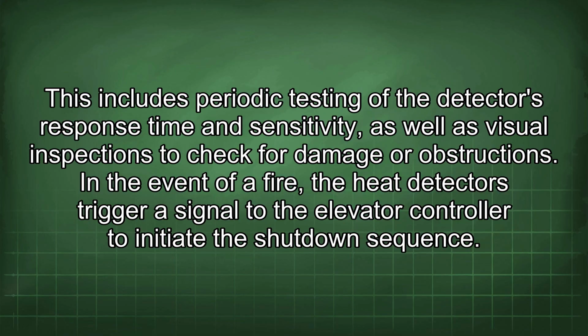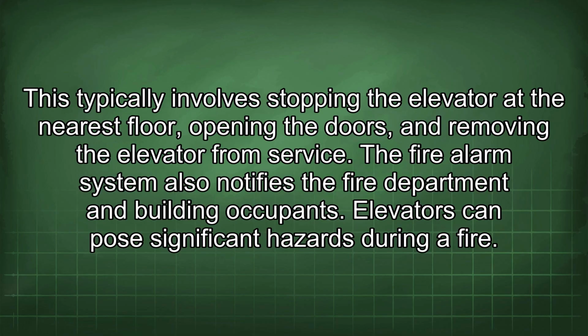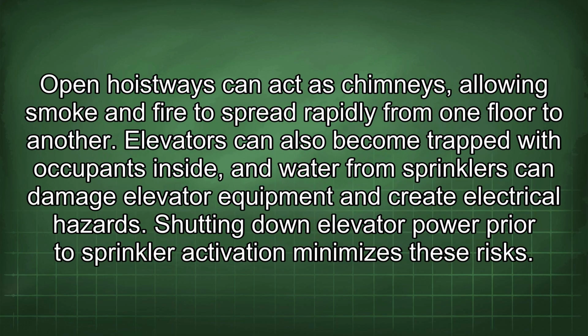or obstructions. In the event of a fire, the heat detectors trigger a signal to the elevator controller to initiate the shutdown sequence. This typically involves stopping the elevator at the nearest floor, opening the doors, and removing the elevator from service. The fire alarm system also notifies the fire department and building occupants. Elevators can pose significant hazards during a fire. Open hoistways can act as chimneys, allowing smoke and fire to spread rapidly from one floor to another. Elevators can also become trapped with occupants inside, and water from sprinklers can damage elevator equipment and create electrical hazards. Shutting down elevator power prior to sprinkler activation minimizes these risks.